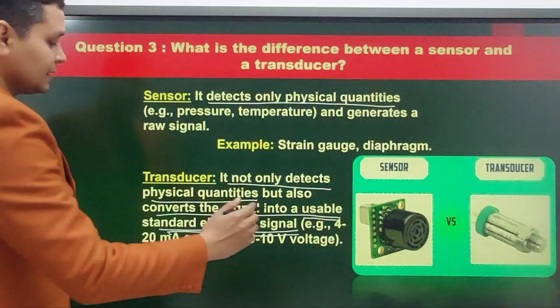Now let's discuss the transducer. We have seen that a sensor only detects physical quantities, but the difference between a sensor and a transducer is that a transducer not only detects physical quantities but also converts the signal into a usable standard electrical signal. Some usable standard electrical signals are 4 to 20 milliampere, 0 to 10 volt. So a sensor only detects, and a transducer detects plus converts.